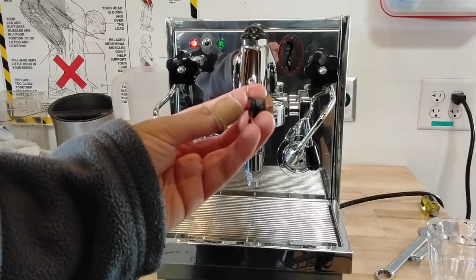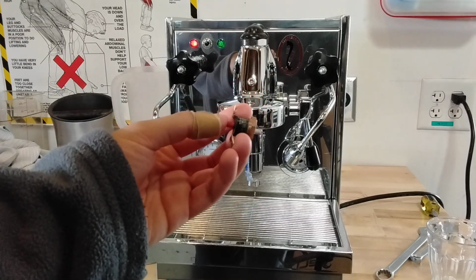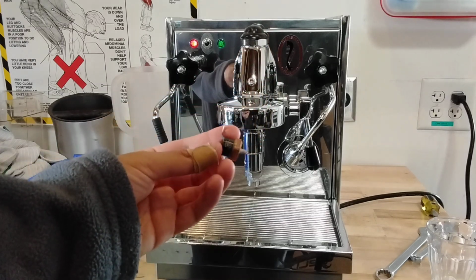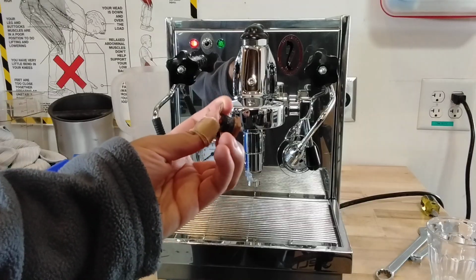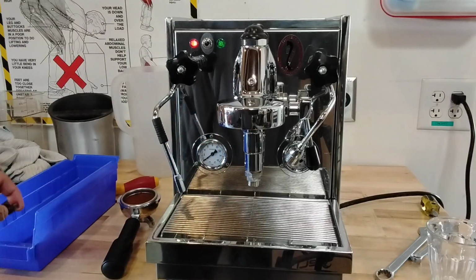So you just had to replace that safety stat. This is allowing the machine or the heating element to receive power or not receive power, so once it broke, it wasn't allowing power to go to the heating elements.